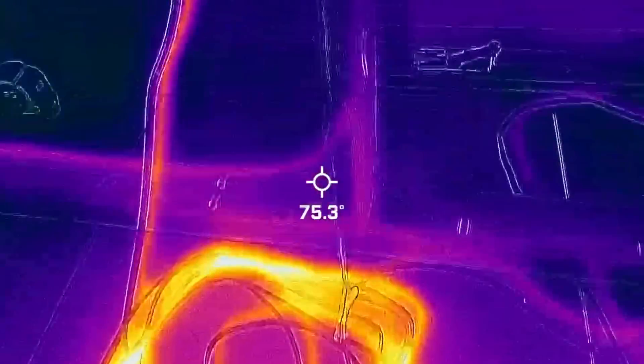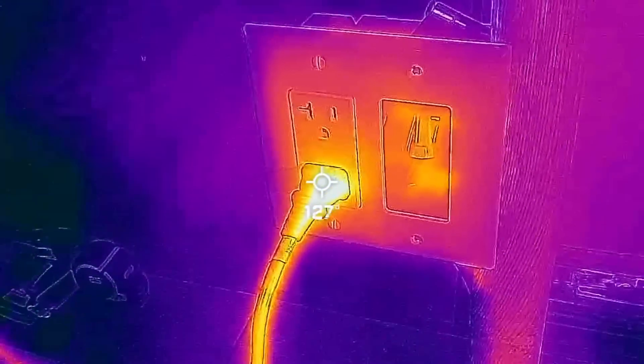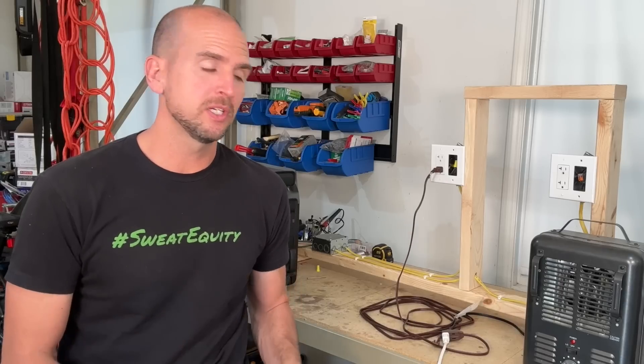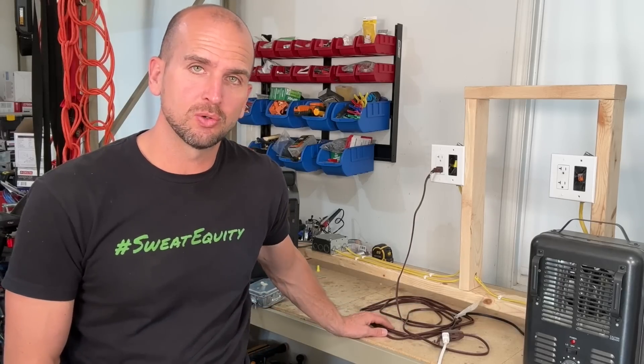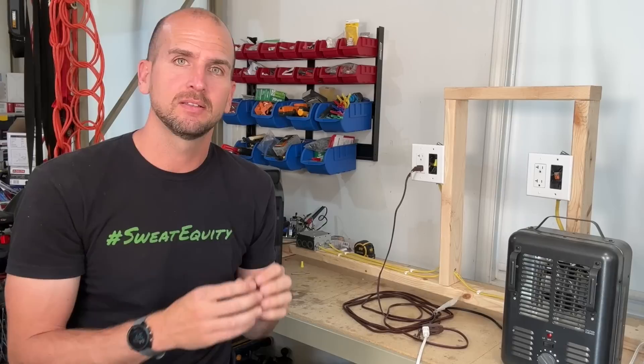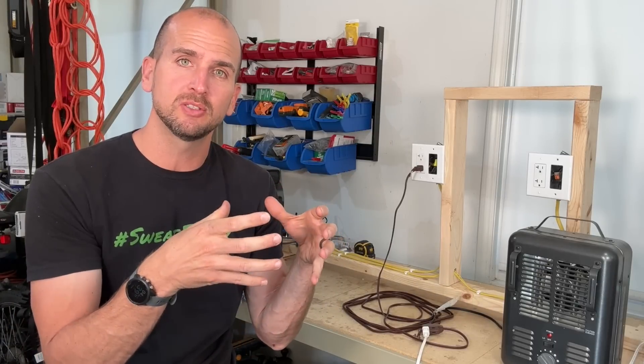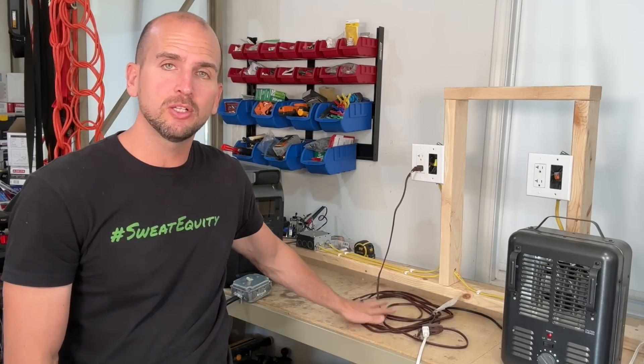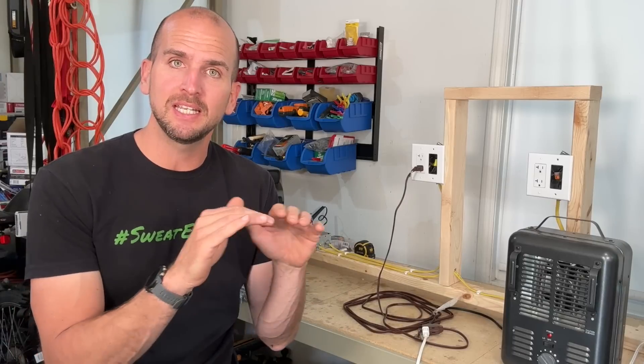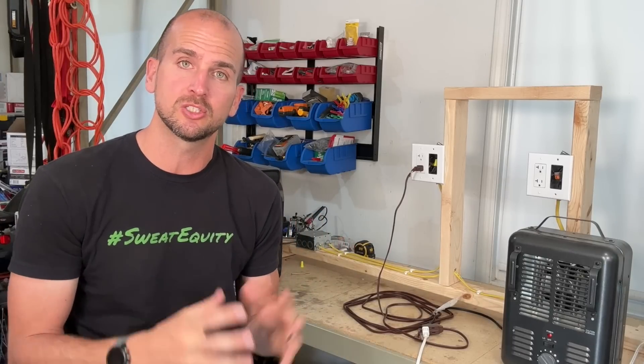After five minutes, using the FLIR thermal imaging camera, our maximum temperature reading is about 130 to 135 degrees Fahrenheit. It should be noted that when you bundle extension cords — with multiple strands stacked on top of each other — that concentrates heat and generates even more. Even worse, if a pillow, blanket, or something similar is covering the cord, it insulates it and reduces heat rejection to the environment.